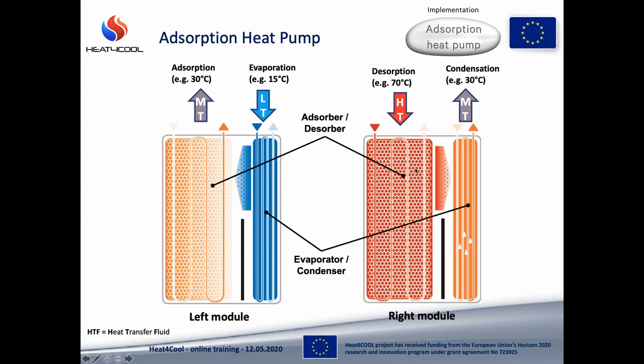On the right side, you see the desorption-condensation phase. Since we have to add heat to the sorbent in order to regenerate it, HTF at high temperature, HT, has to flow through the desorber, warming it up. During the condensation process, similarly to adsorption, the heat is released and has to be dissipated. And here we use HTF at medium temperature again.